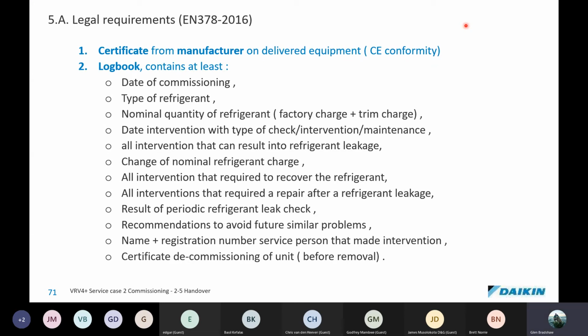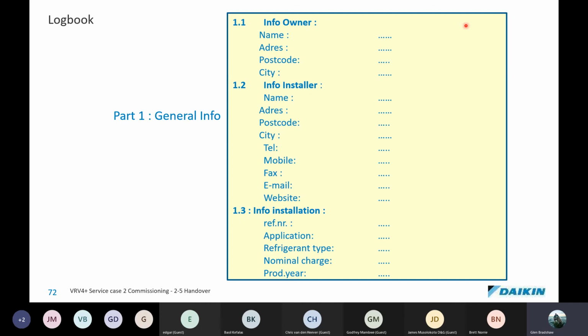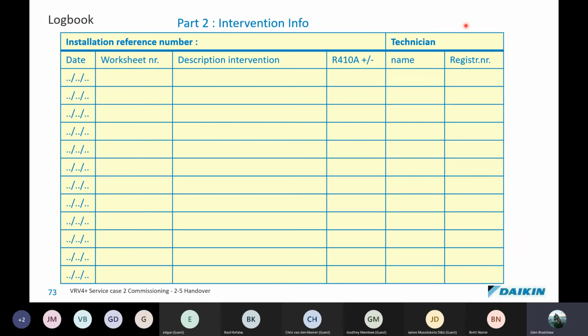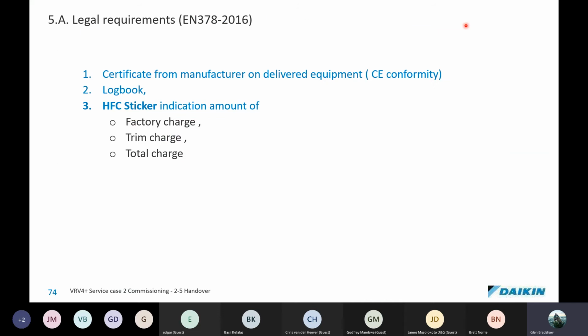One of the things that's supposed to be kept on site with air conditioning installations is a logbook, into which all calls are logged. And if any work is done that required removal or addition of refrigerant, it should be logged in there along with those repairs. So it should have all the general information on there. It could just be a basic table with worksheet number, description, intervention, and the amount of refrigerant added or subtracted.